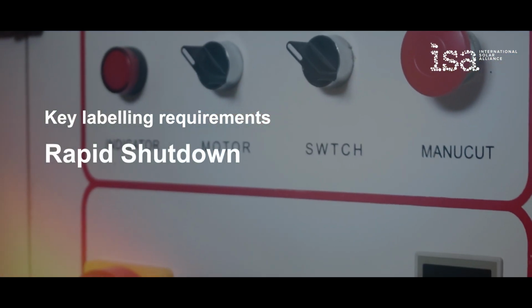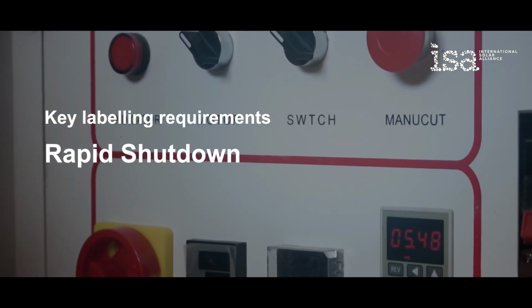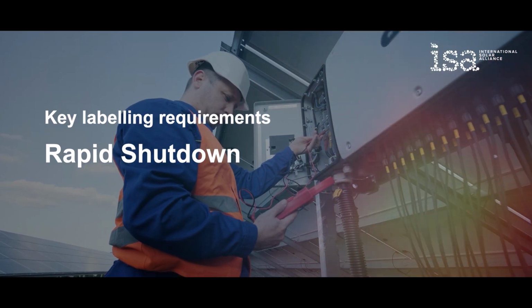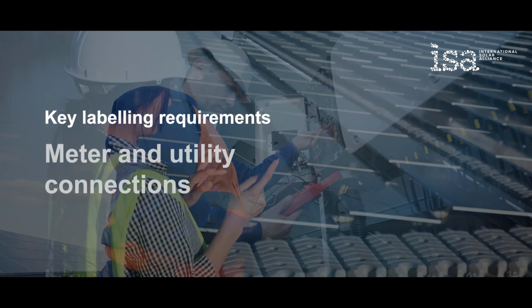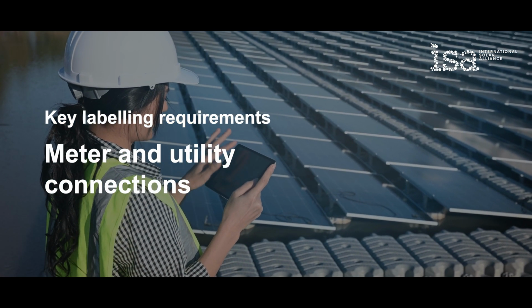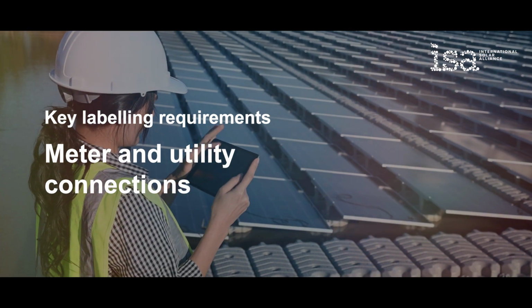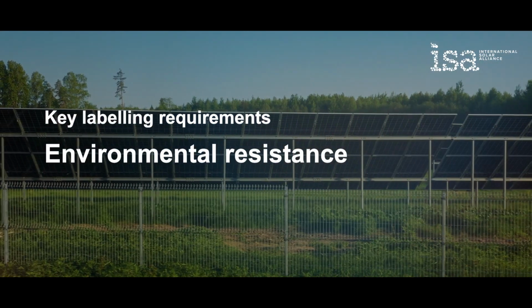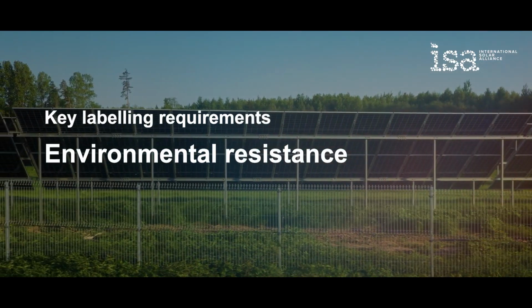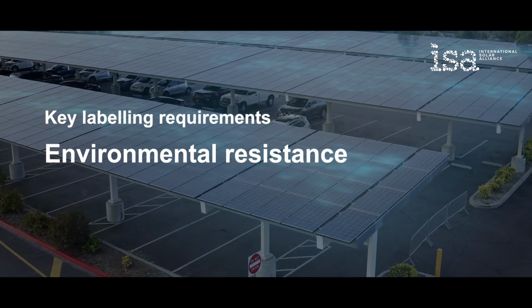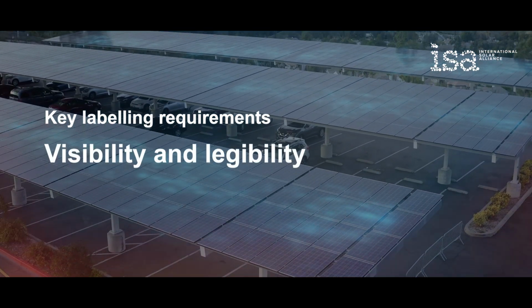Rapid shutdown. Label any rapid shutdown switches clearly, even if they are integrated into another component like the DC disconnect. Meter and utility connections. Label the primary utility meter to indicate a PV system is connected. Environmental resistance. Labels must be durable enough to withstand the elements where they are installed, such as UV exposure, rain, and wind. Visibility and legibility.